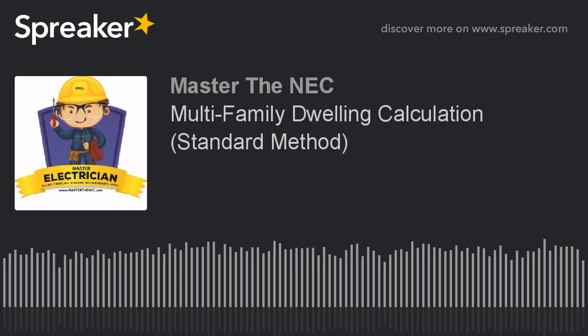So what do we do? We already know our dryer value was 36,000. We're simply going to take the 36,000 times 70%, or 0.70, and that's going to give us 25,200. That's what our neutral current is. Basically, it's 70% of the 36,000 VA. So over in the neutral column, we're going to write down 25,200. Now we have our neutral load for those dryers. We're moving on. The next thing we're going to deal with are the ranges.